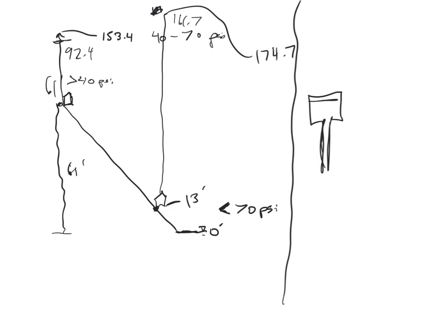Let's say the top water level right here, the max water level we put is 170 feet. I'm not saying that's what you should do, but let's say that is what we did. One of the constraints in your system is that the pump has to be able to fill the tank. Remember that this is on some slope, there's eventually some zero, and your pump is located down here at 0.